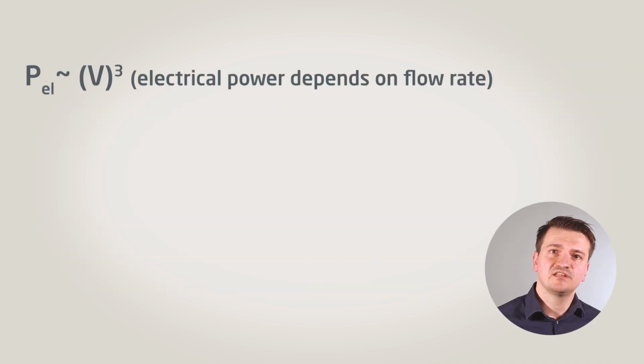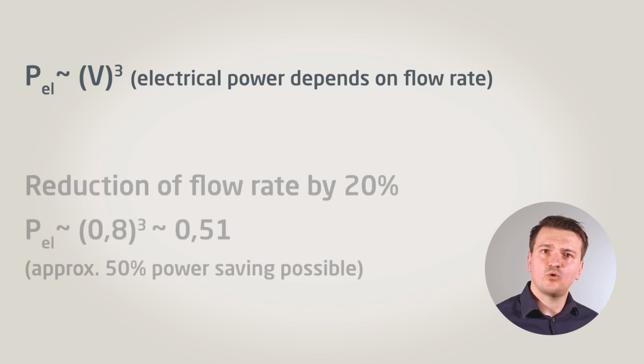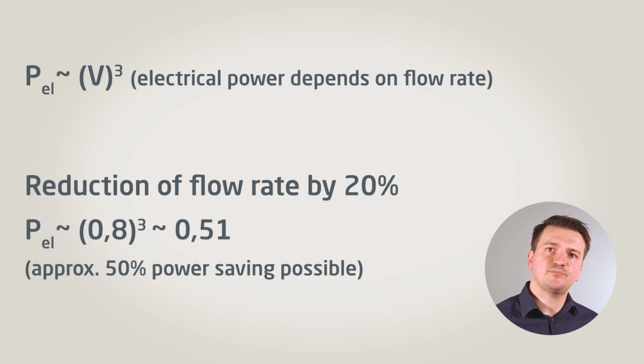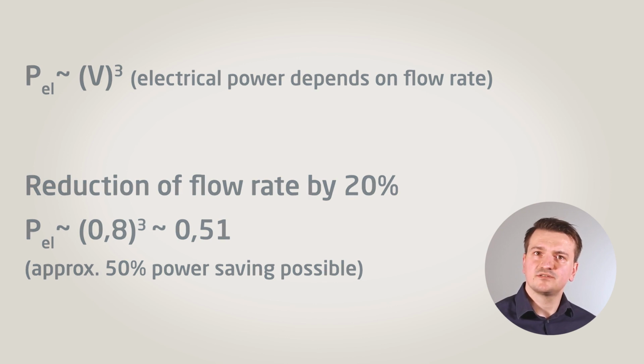Translated, this means that the electrical power, or PEL, is related to the volumetric flow V to the power of 3. If we now reduce the volumetric flow by 20%, which means we only need 80% of the heating oil volumetric flow, the required electrical power is reduced by 49%. You can achieve this with our new control software. I will of course also tell you what exactly is modernized.